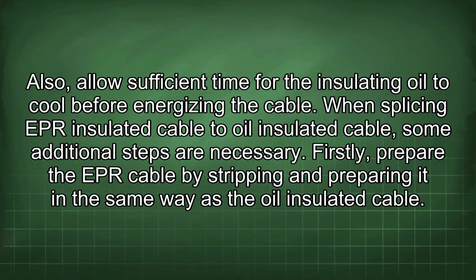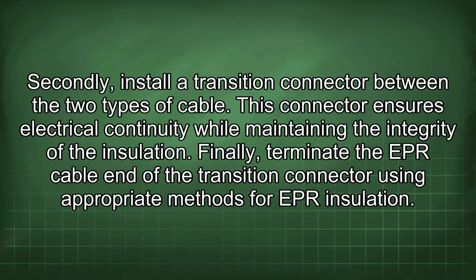When splicing EPR insulated cable to oil insulated cable, some additional steps are necessary. Firstly, prepare the EPR cable by stripping and preparing it in the same way as the oil insulated cable. Secondly, install a transition connector between the 2 types of cable. This connector ensures electrical continuity while maintaining the integrity of the insulation. Finally, terminate the EPR cable end of the transition connector using appropriate methods for EPR insulation.